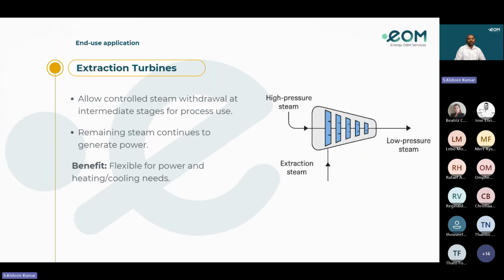Coming to the extraction turbines. An extraction turbine is a turbine designed to extract steam at one or more intermediate stages during its expansion. This extracted steam, at a controlled intermediate pressure and temperature, is used for process heating, preheating feed water or industrial uses, while the remaining steam continues to expand in the turbine to generate more electricity. This allows simultaneous production of power and steam in an efficient and flexible manner, making extraction turbines ideal for combined heat and power applications, industrial complexes, and power plants with feed water heaters.